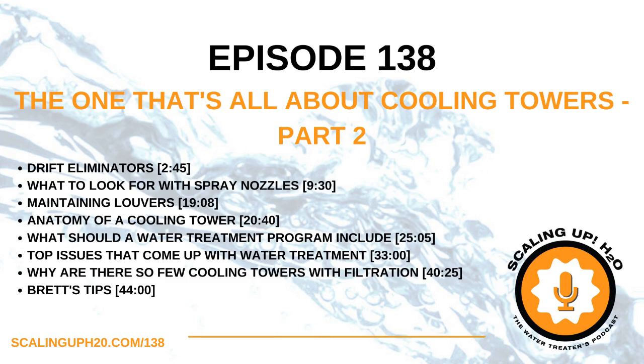So the recommendation would probably be DBNPA. I'm not sure if ISO or GLUT would have any effect unless you're locking out the blowdown for an extended period of time. So just keep in mind, it's a lower water volume and a higher turnover rate in these units.